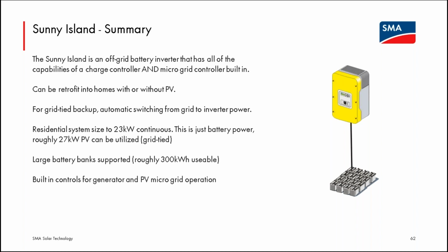The excess power has been removed, but it's not as elegant as having the inverter respond between, and this is what the Sunny Boys are set to as default in off grid, between 61 hertz, let's say it was producing 3,000 watts. It will go from 3,000 watts to 0 watts linearly between 61 hertz and 62 hertz. So the Sunny Island for frequency shift power control will go above 61 hertz and keep rising until it sees 0 net backfeed coming to it. The PV power is allowed to exactly balance the load demand and the charging demand. And so the Sunny Island will range the AC frequency between 61 and 62 hertz to achieve that. It doesn't then need to pull from battery power to provide for the loads. It simply controls the PV power.